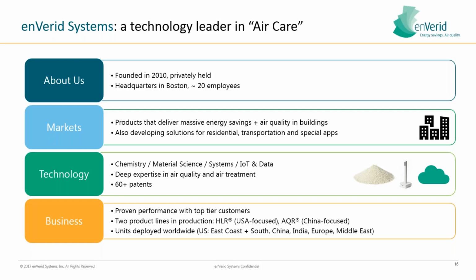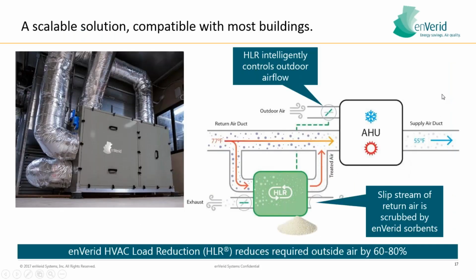enVerid has units deployed worldwide. We have airports in Singapore. We've done projects all over the Middle East and Europe and France and India. And our highest density of applications is indeed in the US South and East Coast, where humidity and really hot temperatures really impact building design. Anywhere where you end up with outside air conditions or economizer mode not being used as frequently, this is a great application to see energy savings and also utility rebates as well. The enVerid solution is actually eligible for utility rebates based on energy savings from outside air reduction.